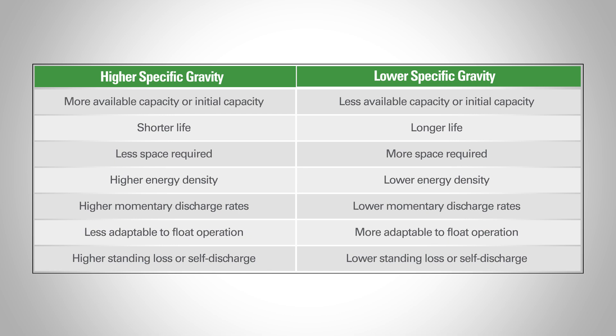Lower specific gravities will give you less available capacity and lower initial capacity, but typically provide longer life. More space is required because lower specific gravity delivers lower total capacity and lower energy density. You'll get lower momentary discharge rates, but lower specific gravities are more adaptable to float applications and result in slower self-discharge rates.